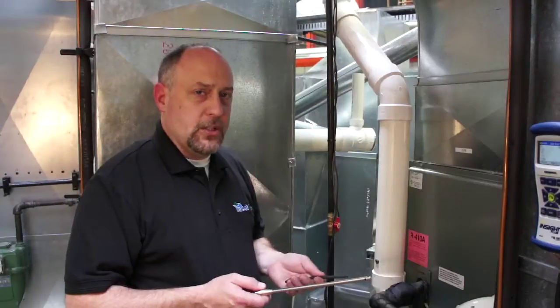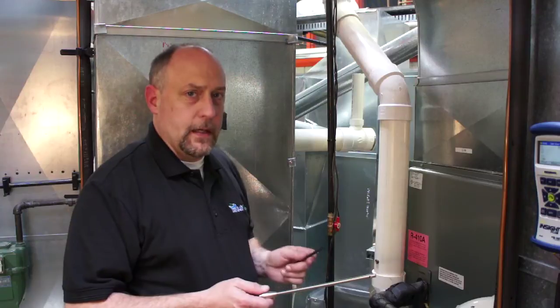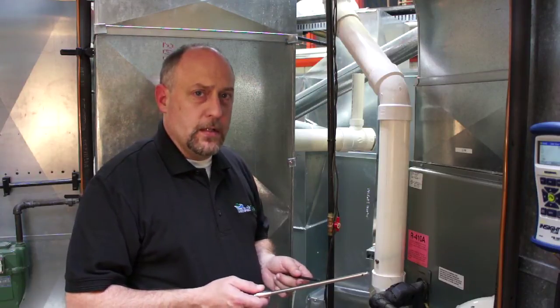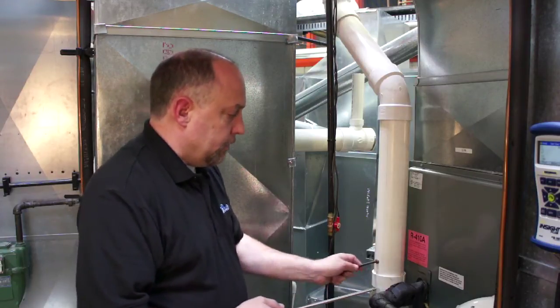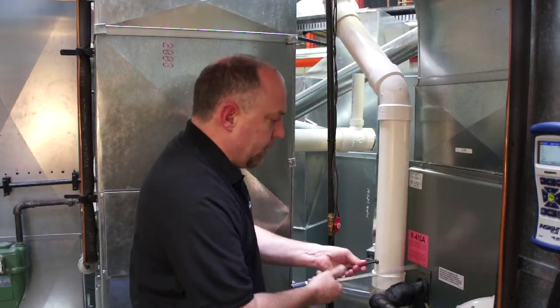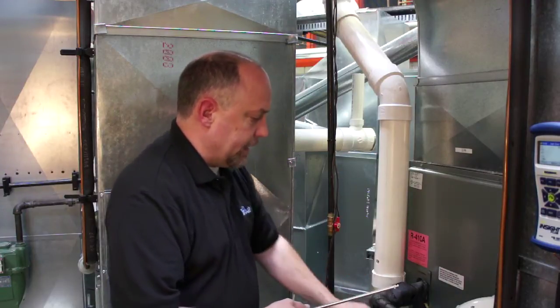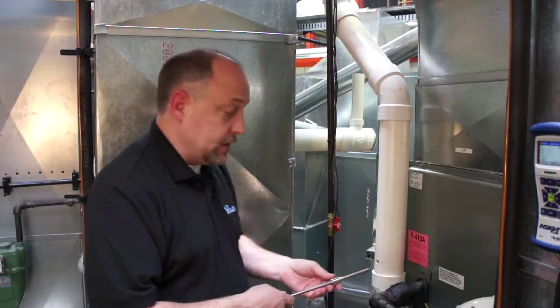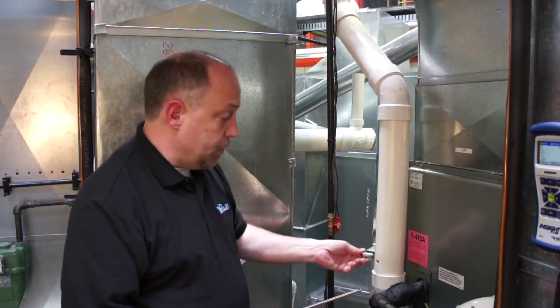All right, so let's get this instrument in the stack gas, and we'll get a look at some of the other menus and things that it does. And so we're going to go ahead and put this in, and whenever you're doing this, this is a category 4 vent again, so you want to make sure you're not leaking flue gas into the space. So you definitely want to use the probe stop in here.